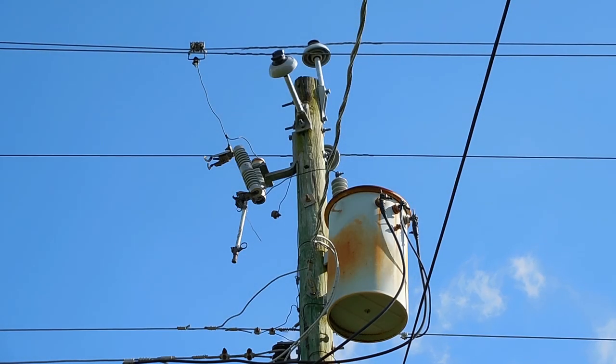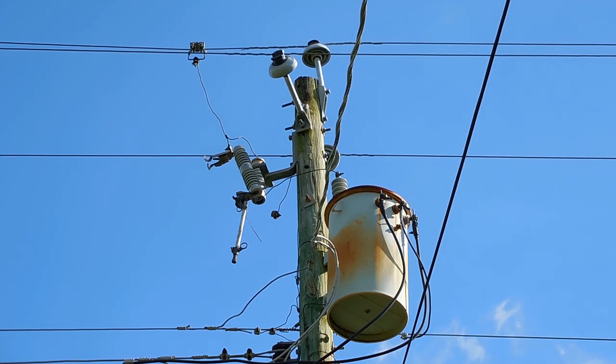And as you just saw, that was not very good. Went to reset the switch, you heard the sound it made, and it popped back down. That's an indication that the primary winding in the transformer is faulty.